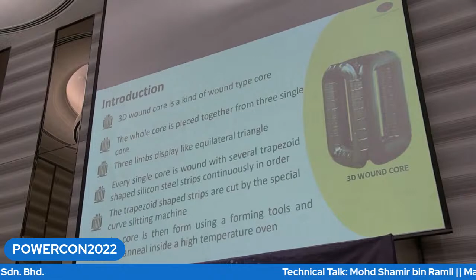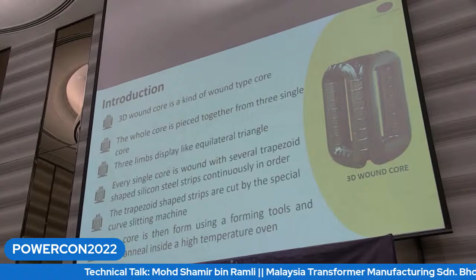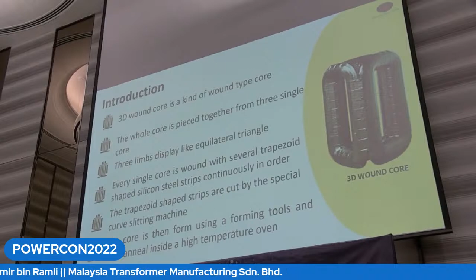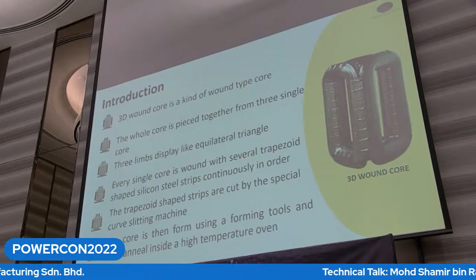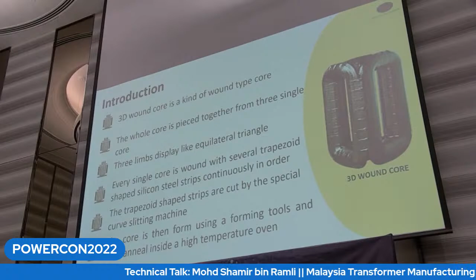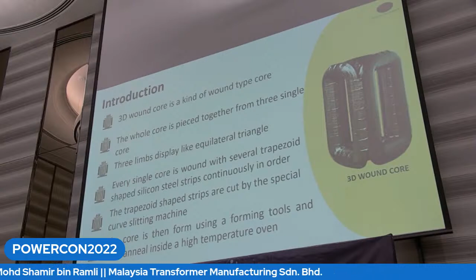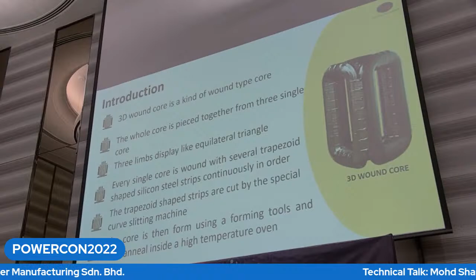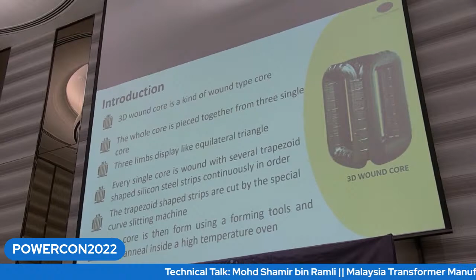3D wound core is a kind of wound type core transformer. Many of us are familiar with the conventional transformer, but the 3D wound core is pieced together from 3 single cores, like a triangle. The 3 legs display like an equilateral triangle, and every single core is wound with several trapezoid-shaped silicon steel strips continuously in order. These trapezoid-shaped strips are cut by a special curve slitting machine, and the core is then formed using forming tools and annealed inside a high temperature oven to give the core stability.